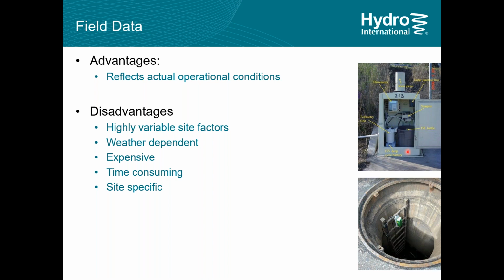So the advantages of field data, it does reflect the actual operational conditions. Disadvantages, it's highly variable. You don't own the site generally. You don't have 100% control of the site. Of course, it's weather dependent. That's the whole point of it. It is expensive and time consuming. And it is kind of site specific. You can move a piece of equipment from one site to another. They can be side by side and get two completely different results, even though they may be the same size.